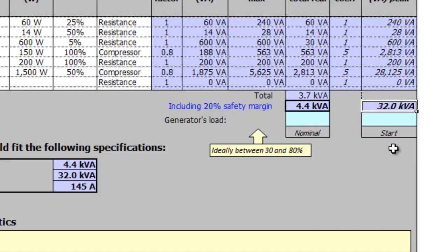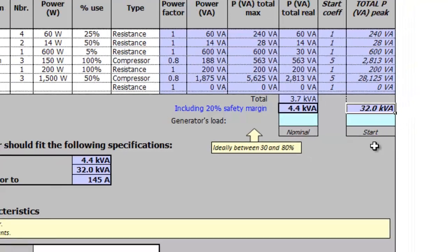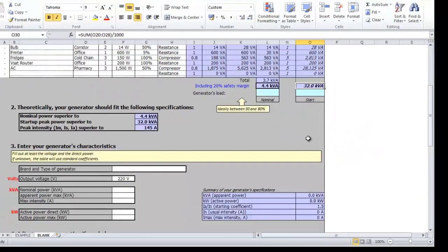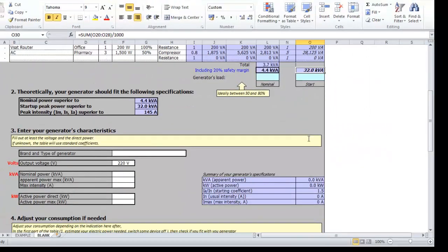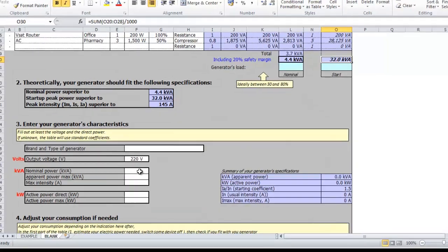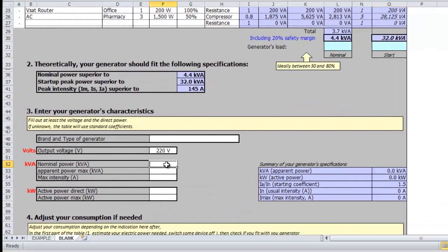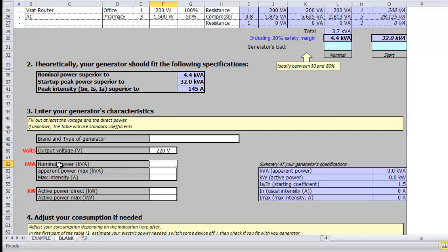With this information the tool shows at which percentage of its power capacity the generator will work and if it can handle the peak current if all the appliances were started at the same time. The generator shouldn't be either too big or too small and ideally it should work between 30% and 80% of its capacity.